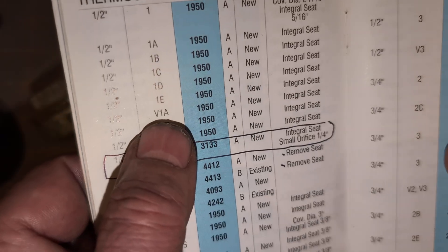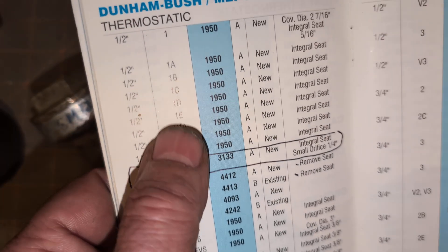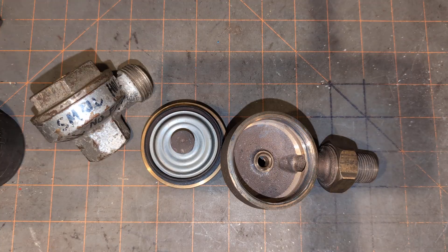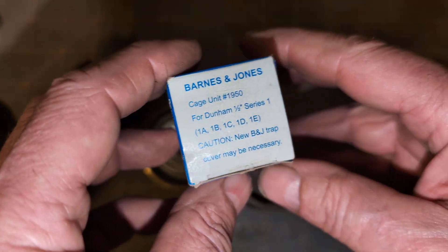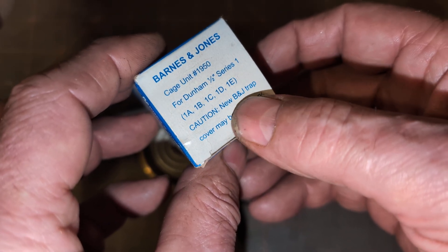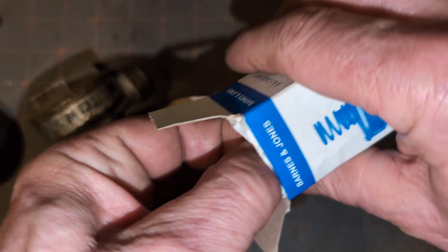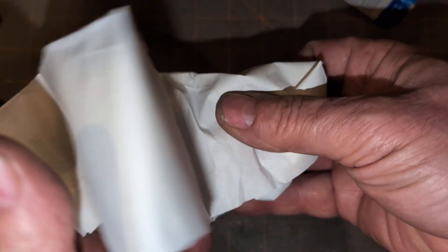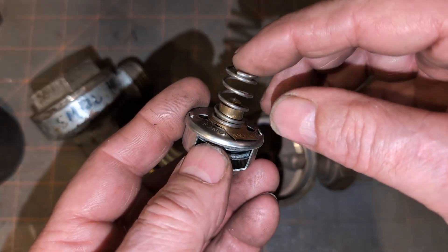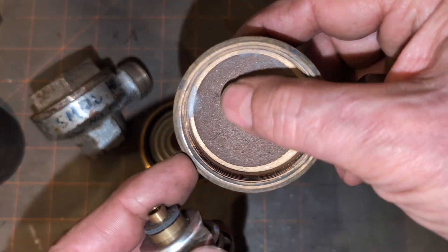Only the number 1 requires a different cartridge unit and has the small orifice. You've got a couple of other versions. V stands for victory, which means it was during World War II when they stopped using brass, because brass is a strategic alloy, and steel was cheaper. It calls out for a 1950. We can see it has all the different sizes, 1A through 1E. Caution: a new Barnes & Jones trap cover may be necessary. We opened it up and we'll find the new cartridge inside.